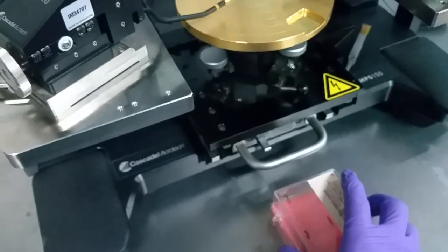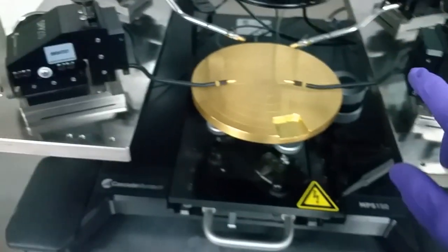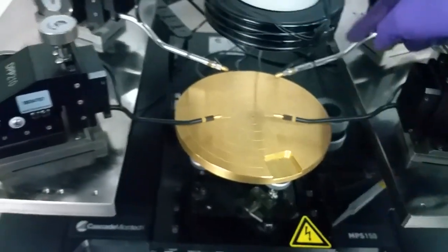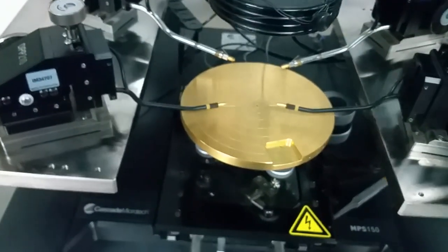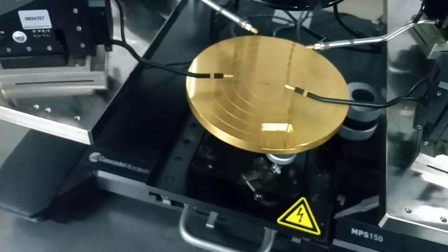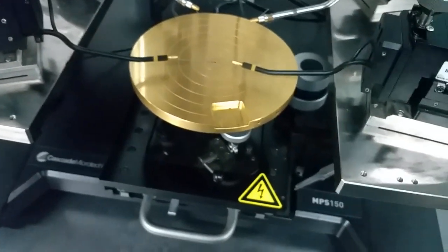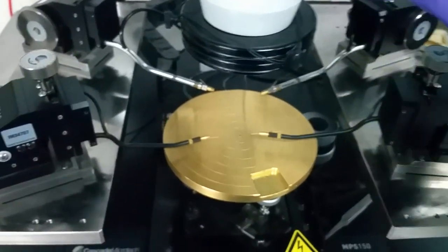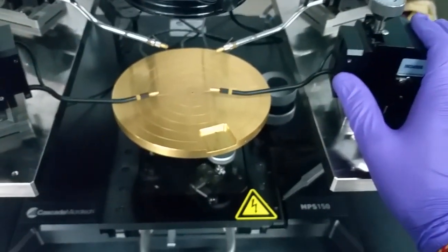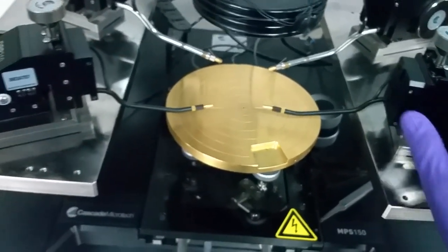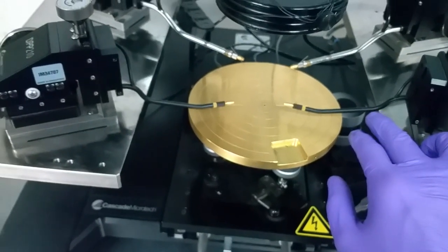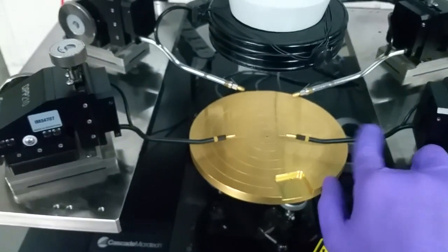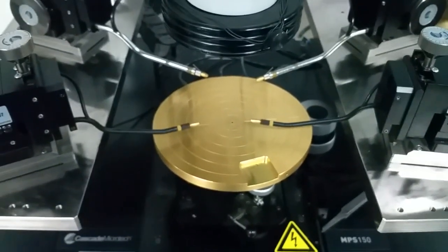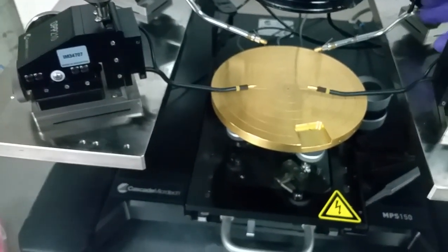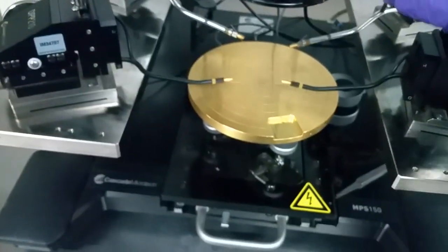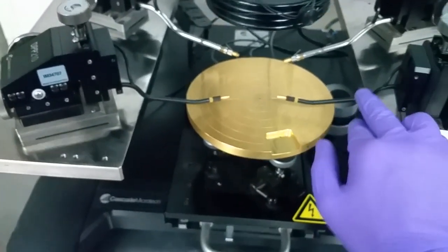So this is about the probe station. One thing I forgot to tell you, that here we have different probes. Like we have a biax cable here, this one black colored, and this is the triax cable. So this is used for low current measurements, like this triax cable. Normally we prefer to use it for low current, like below the nanoampere range. And suppose if you want to do some high current measurements, or say high frequency measurements, like CV measurements, then you should use these cables. These are biax cables, which are further connected to BNC connectors or BNC cables. So for low current measurements, you should use the silver cables, which are triax cables, and for high current or CV measurements, you should use these black cables, which are biax cables.